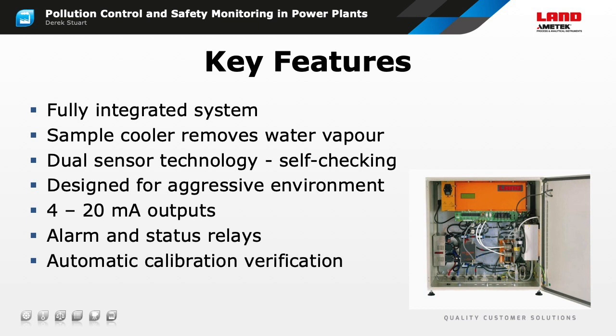The Land Silowatch monitor is specifically designed to measure CO in a silo headspace. It's a self-contained unit combining CO sensors with sample conditioning, signal processing, and calibration verification in a single cabinet. It's engineered to be robust and to function reliably in a plant environment. As well as its alarm functions, it gives a 4 to 20 mA analog output, so you can follow trends in the silo CO concentration.